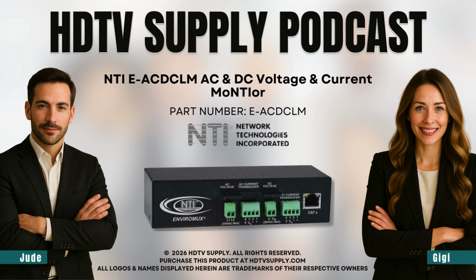So for the current measurements, if the transducer is doing all the heavy lifting, what is the E-ACDCLM itself actually contributing? It's providing the vital interfaces. It has one rectifying interface for AC current, so it converts that signal, and one non-rectifying interface for DC current. And the resolution is high on both. Very high, 0.2% resolution, which ensures the data stream back to the main ENVIROMUX unit is precise. And it's fast, polling at 1 sample per second.